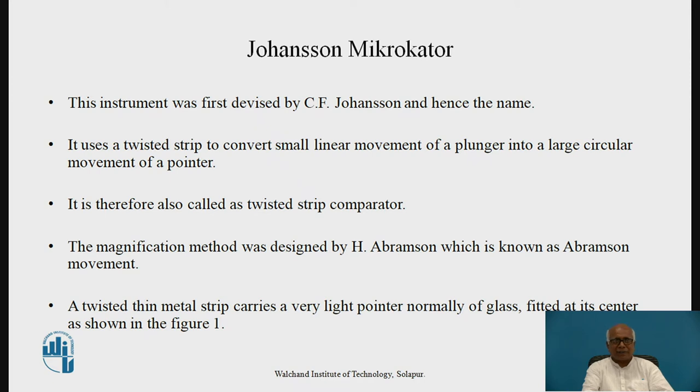First, the Johansson Mikrokator. This instrument was first devised by C.F. Johansson, and hence the name. It uses a twisted strip to convert small linear movement of a plunger into a large circular movement of a pointer. It is a simple device, therefore also called a twisted strip comparator. The magnification method was designed based on the principle devised by H. Abramson, which is also known as the Abramson movement.